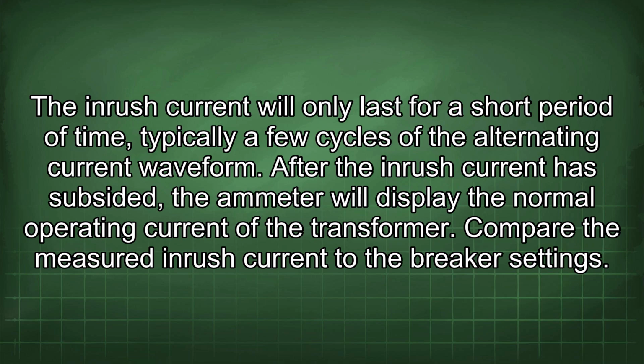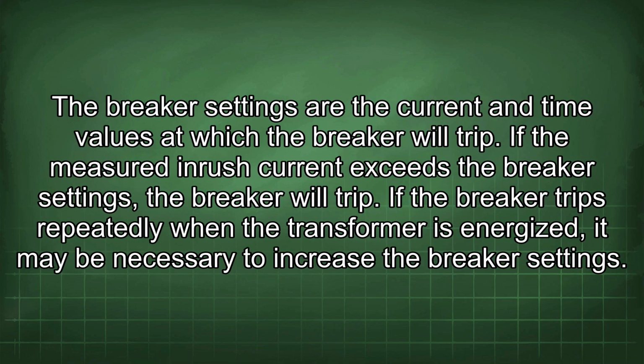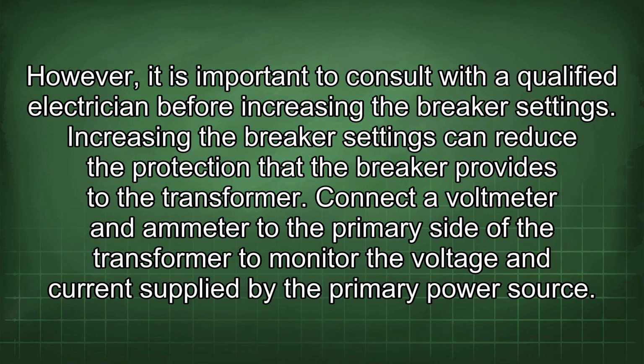Compare the measured inrush current to the breaker settings. The breaker settings are the current and time values at which the breaker will trip. If the measured inrush current exceeds the breaker settings, the breaker will trip. If the breaker trips repeatedly when the transformer is energized, it may be necessary to increase the breaker settings. However, it is important to consult with a qualified electrician before increasing the breaker settings. Increasing the breaker settings can reduce the protection that the breaker provides to the transformer.